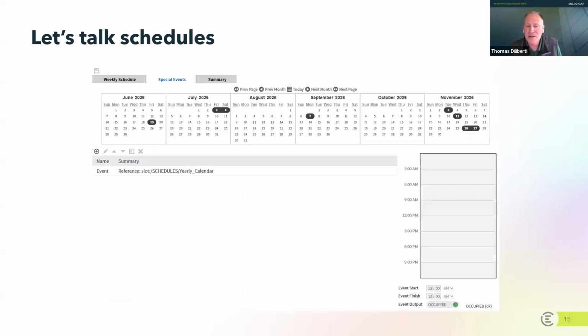And finally, regarding schedules, this is an example of those special event schedules. This menu allows you to take the different months of the year and identify dates that you might want to operate your building in a different way. If you notice here, the dates being flagged on this exception schedule or event schedule are holidays. These are unique dates where you might want to remain in an unoccupied mode.